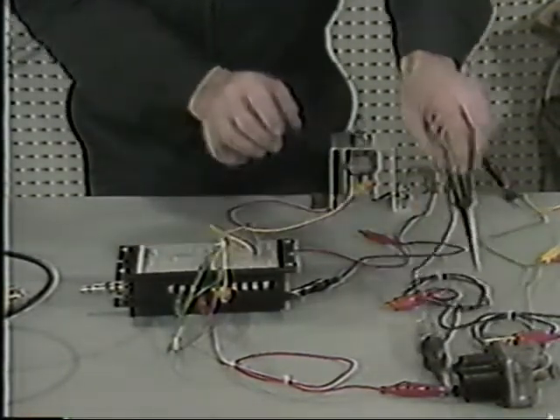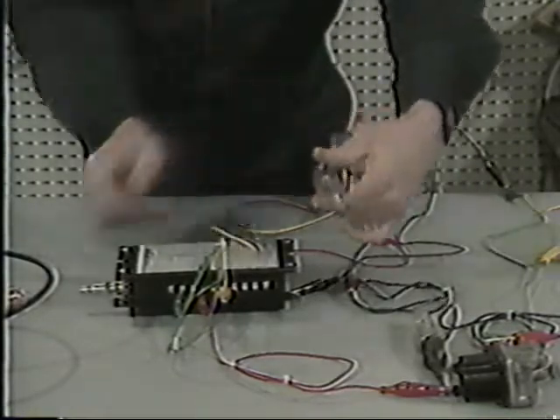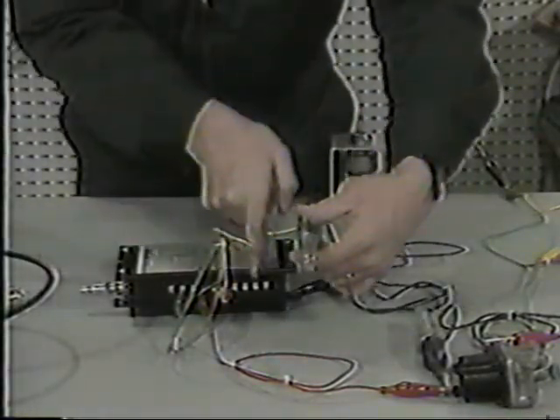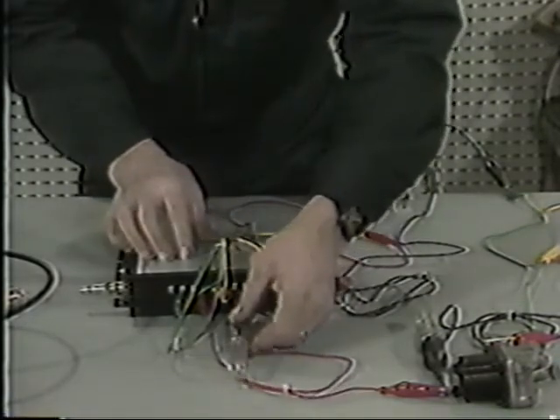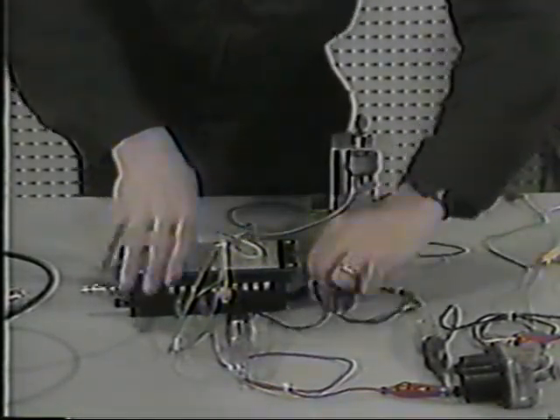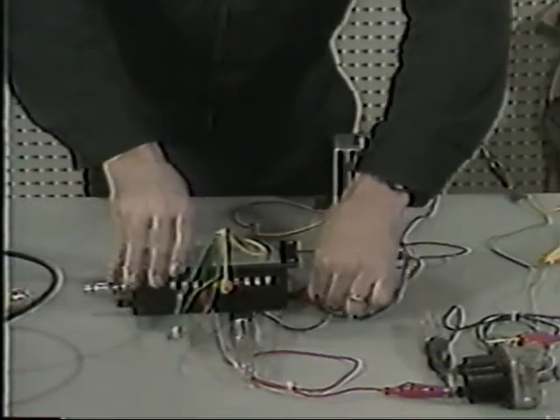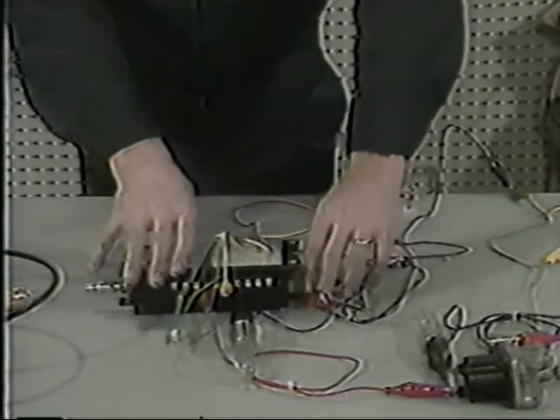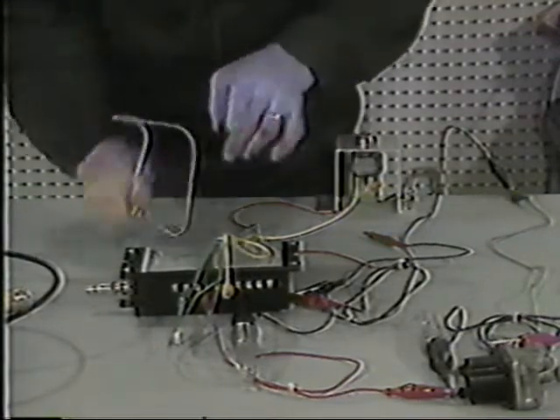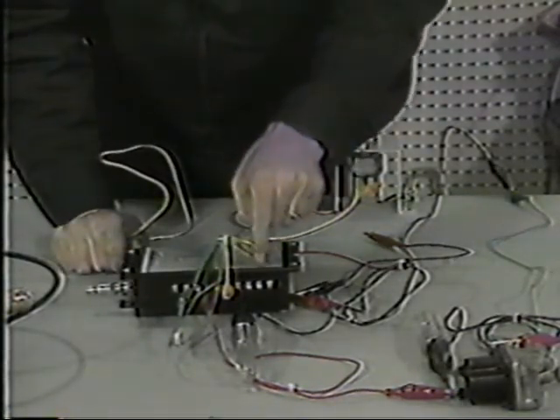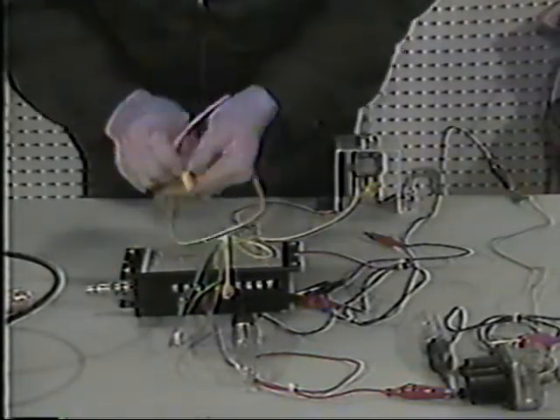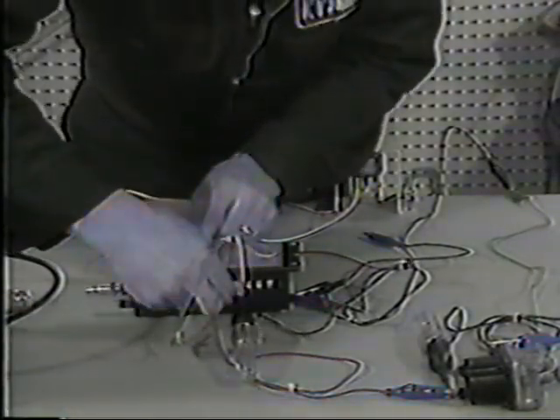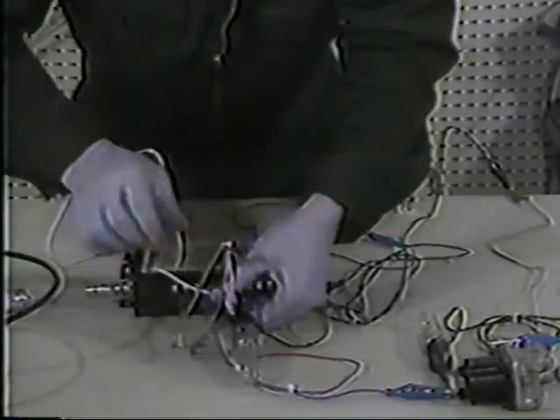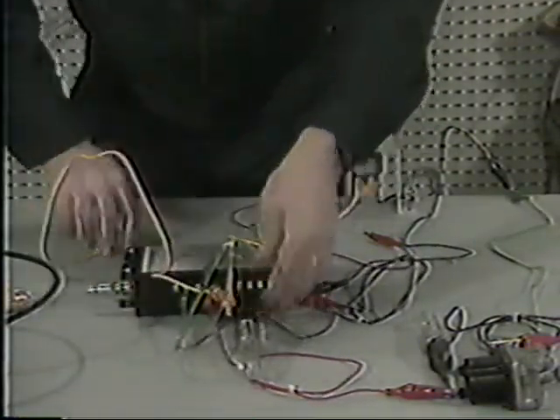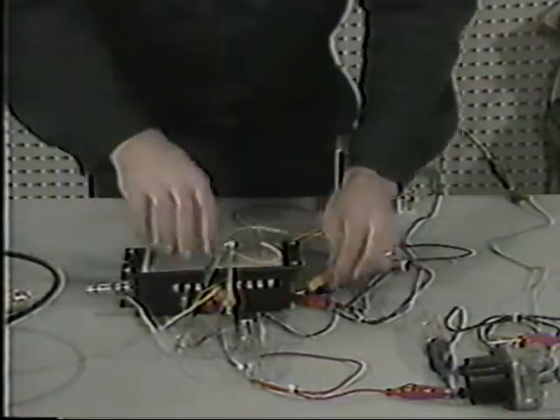Take a second test light and connect it to the alarm terminal of the module, which is the 3rd one down. Ground the other end of the test light at the mounting tab. Take another jumper wire to the water terminal on the module if this is a 3-way unit. This is terminal number 5. Take that jumper wire also to the mounting ear, so it will be grounded.